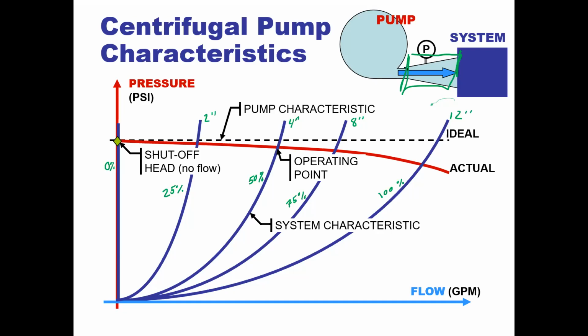It won't overpressurize to breaking because it will only go to the height of its ideal. So it still stays technically inside of its characteristics where it's built to be at. So if we're not moving any more fluid into that area, whether from the discharge of that pump to the valve or wherever that obstruction is that's making this a no flow scenario, it could be 6 inches, 12 feet, doesn't matter. We're going to be adding no more fluid.